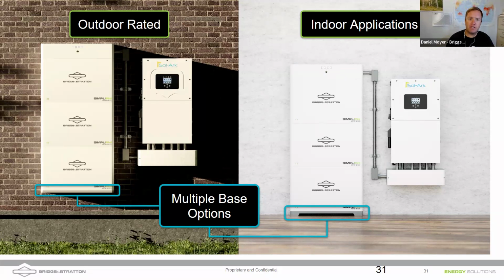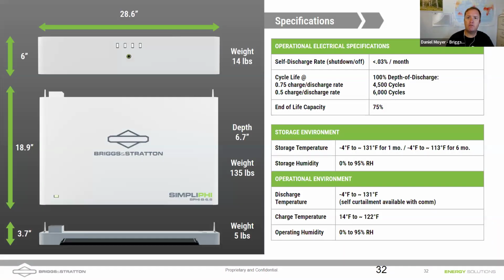I think that looks like 3/4 or maybe 1 inch there as well. Yeah, if you're doing 4-aught cabling, you could probably get away with 1.5 inch, but you really want to use a 2-inch conduit. And if you're going outside, you want to make sure that you're using something that's watertight, obviously.